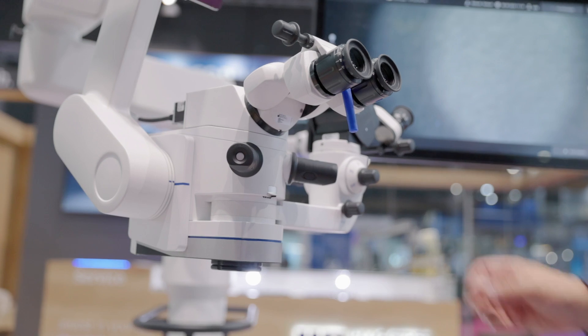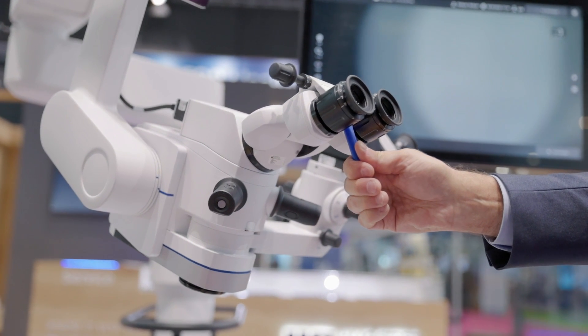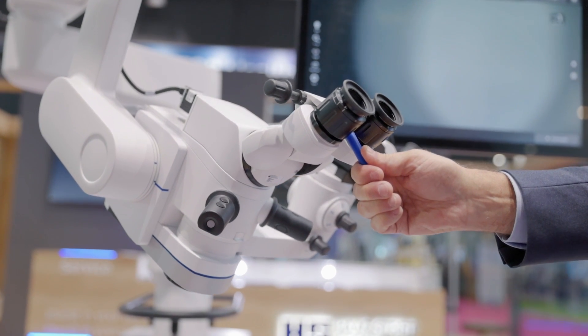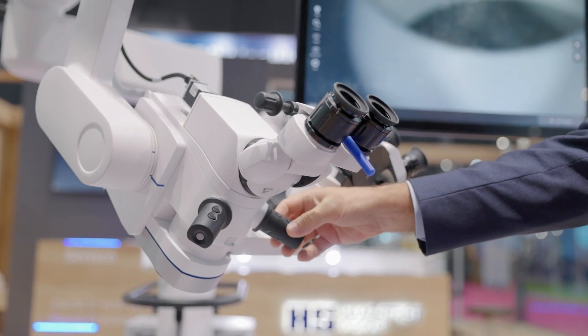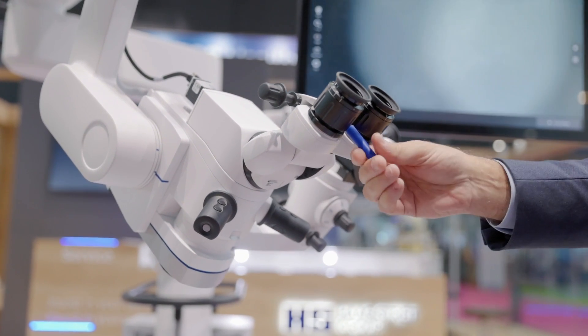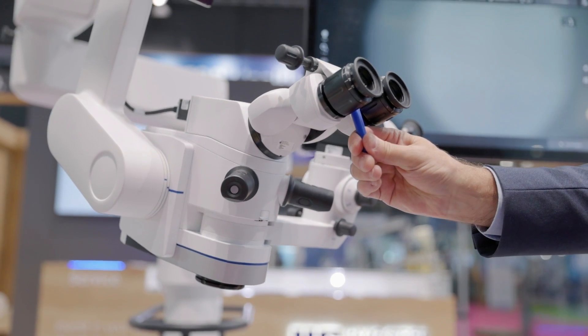One of the key innovations on the microscope is the ability for it to tilt into a glaucoma position with a motor. The surgeon can activate a button on a handpiece and manually move it into position, or they can use a preset — just by hitting one button, that brings the microscope into position.